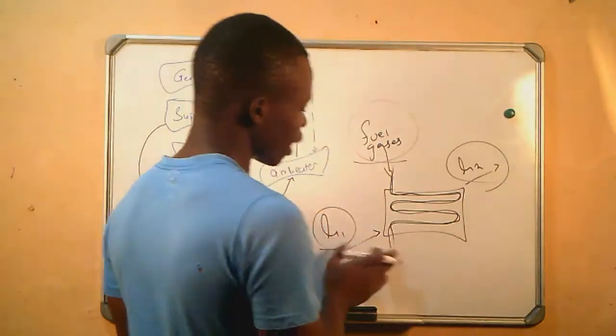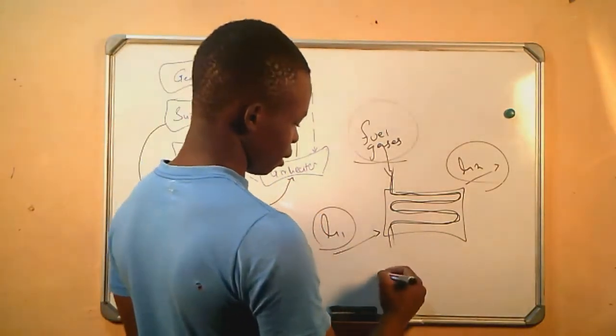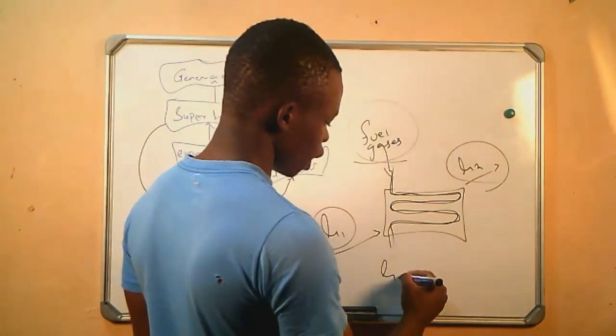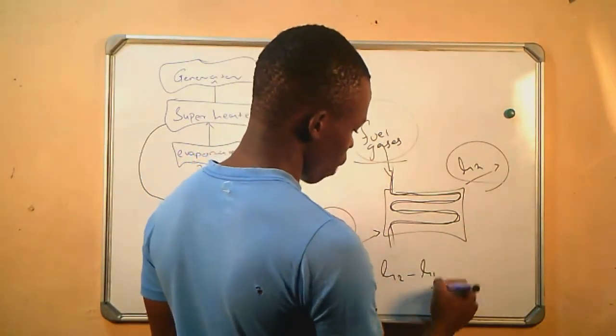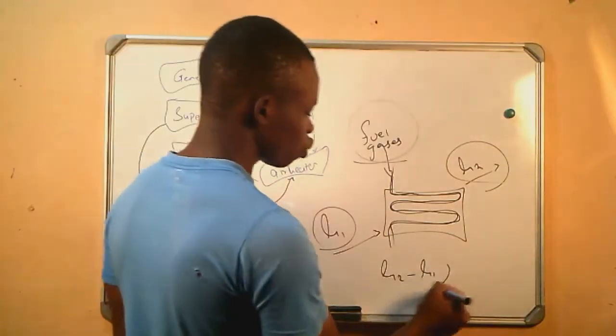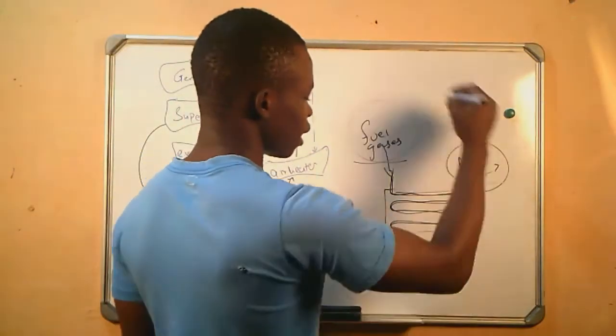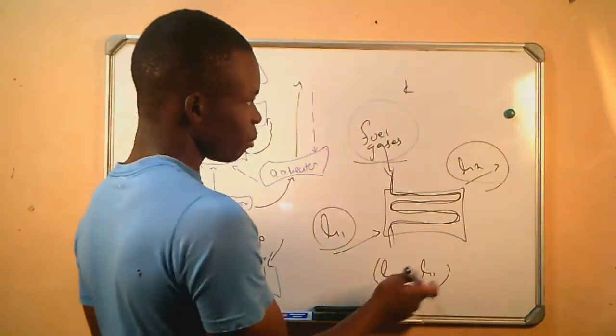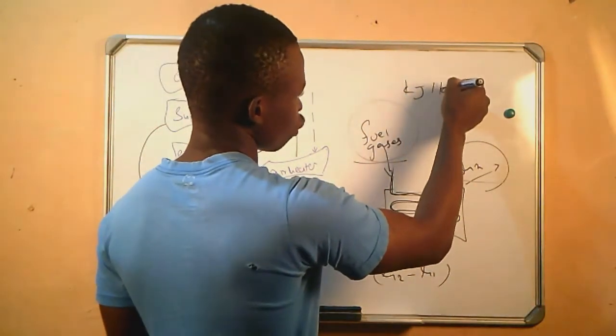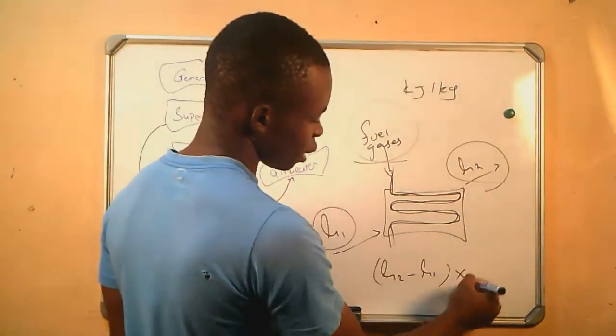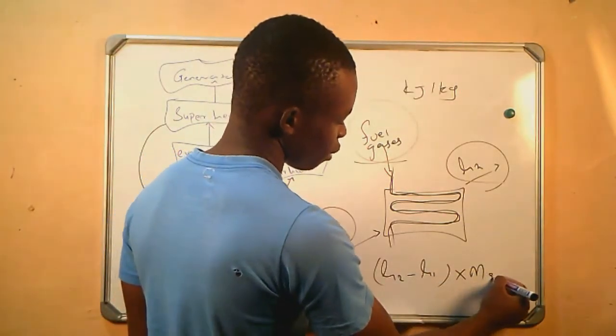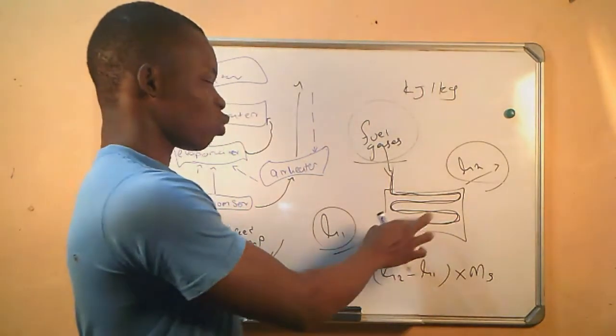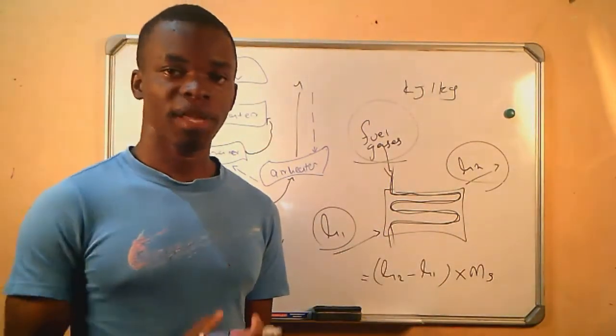To get the heat energy that was gained by the water from the economizer, we are going to say H2 minus H1. This will give us the specific enthalpy, since the SI unit from the steam table is kilojoules per kilogram. We then multiply by the mass of the steam to get the actual amount of heat that was received by the water from the economizer.